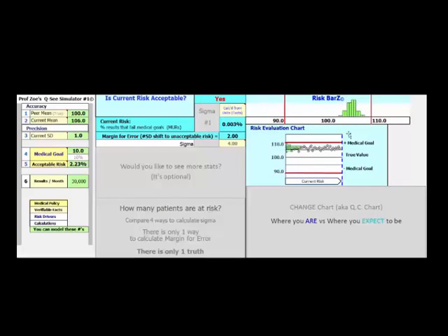You can see visually that it's getting closer. And now it's not quite 0%. This is still a margin for error of 2 or a 4 sigma method. So we've shifted 2 SDs. Let's go up one more to 107. This method can only shift 1 standard deviation before it will fail. This is a 3 sigma method.